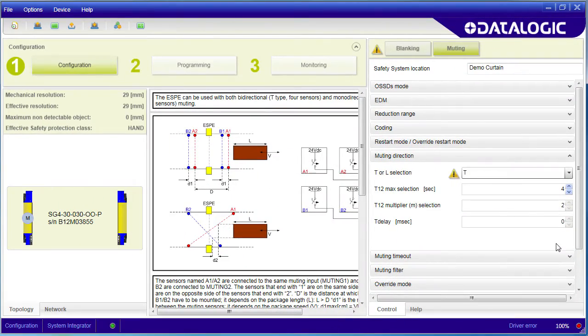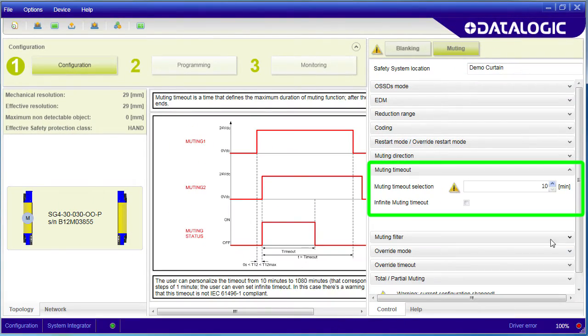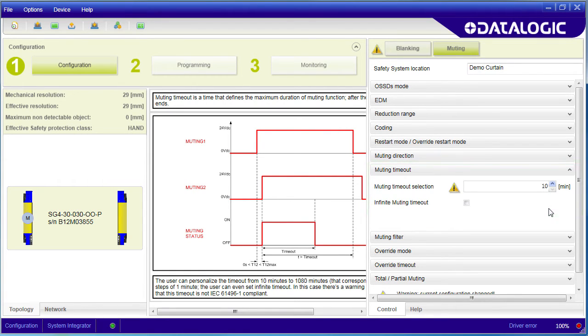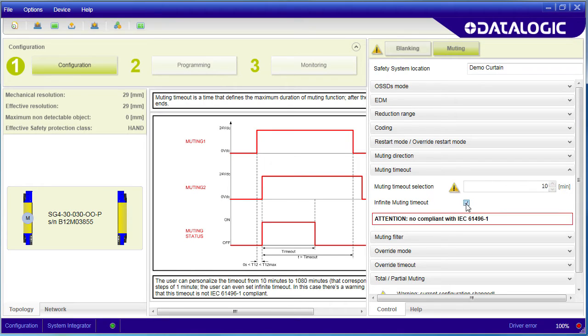Since muting stays active as long as both muting signals are active, we need a way to detect if they get stuck so we can force muting to time out after some length of time here. We can also say we want muting to stay on forever once it's triggered.